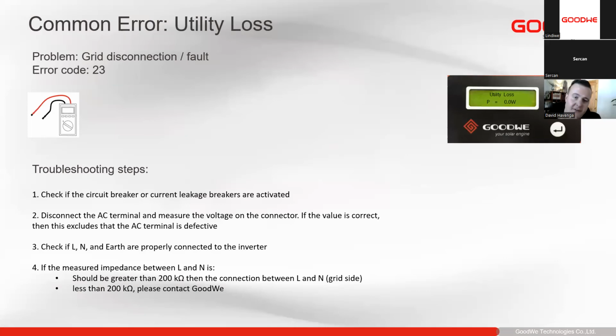Next, if everything's okay, the utilities are on, our breakers are on, nothing has tripped, and the inverter is giving utility loss, then we need to measure under the inverter. Some of them have a cover we can disconnect and measure there, or we can unplug. So switch our AC off, unplug from the inverter, switch it on again, and test the terminals to see that the grid voltage is there. So we need to make sure those terminals are all well connected to the inverter.